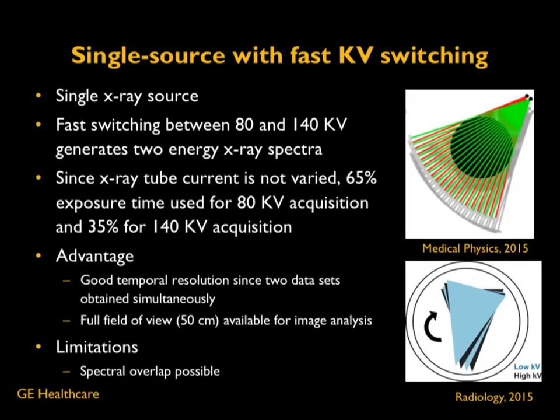The first method is single source with fast kV switching. GE Healthcare has chosen this path, using an existing multi-detector CT scanner such as a 64 or wide-detector CT. The source is a single x-ray tube; however, dual energy is achieved by fast switching of the tube voltage. Rapidly switching between 80 and 140 kV generates two energy x-ray spectra, as shown in this drawing.